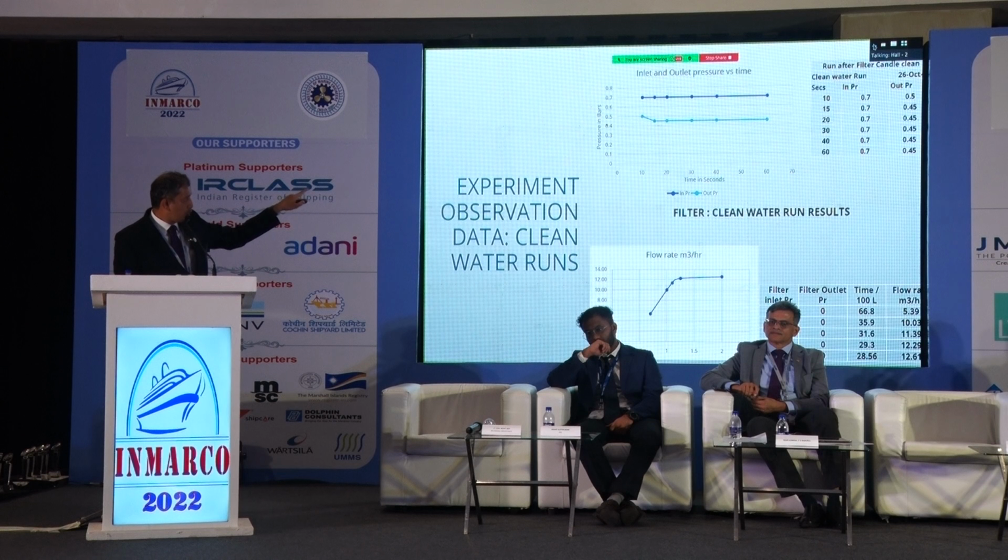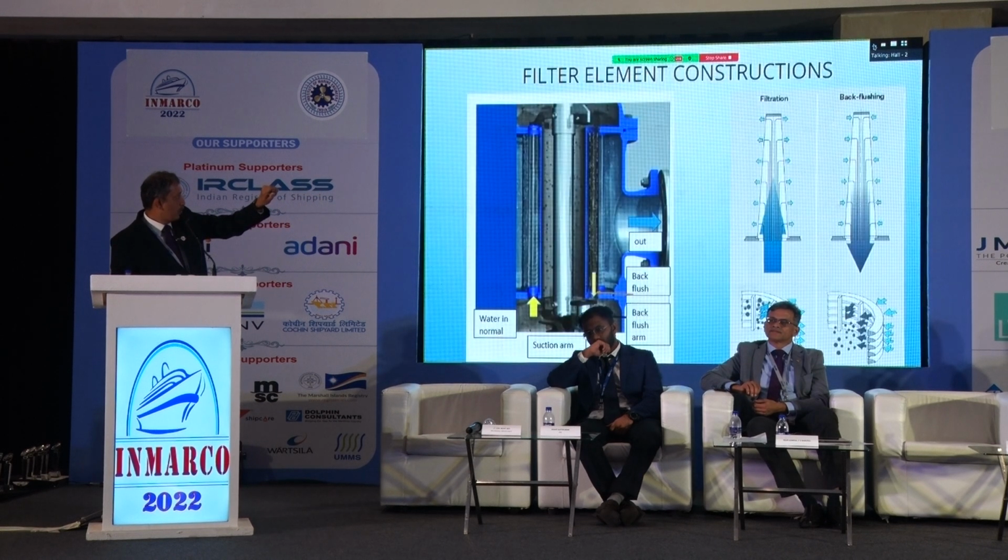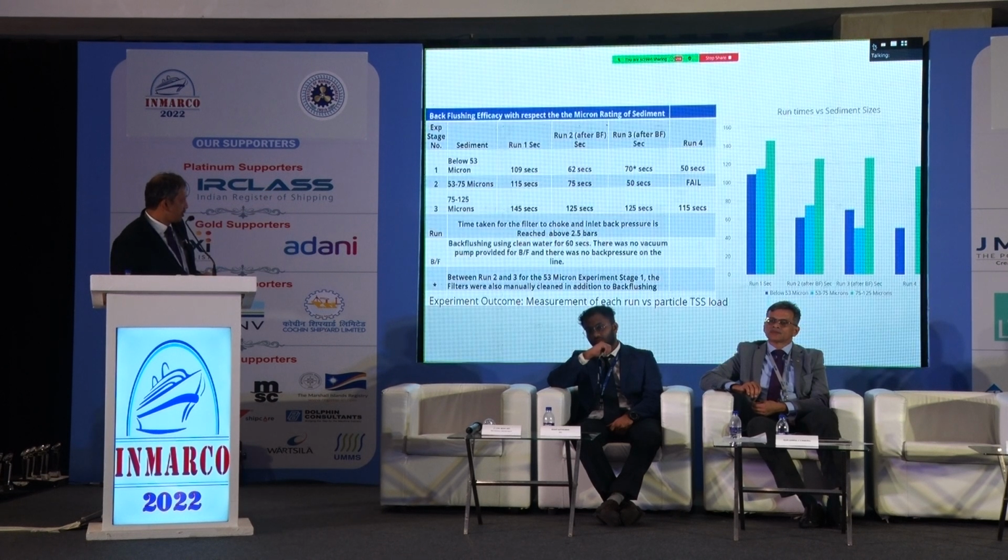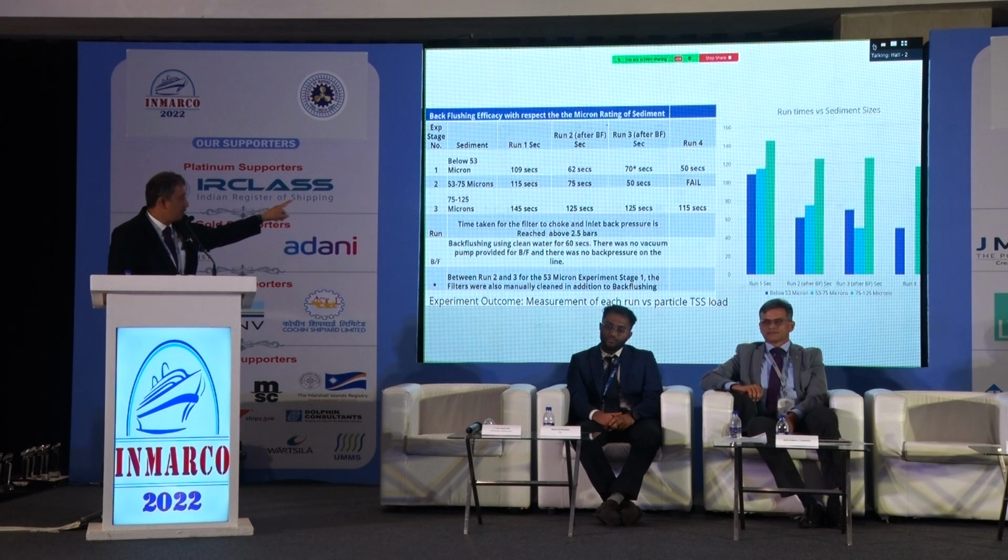So each flow with each micron size, we ran it. The clean water results. Okay, so this is where the interest comes from. Below 53 microns, my clean filter ran for 109 seconds. 53 to 75, ran 115 seconds. 75 to 125, ran for 145 seconds.